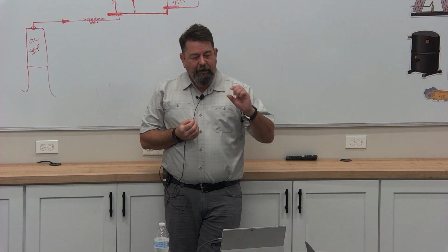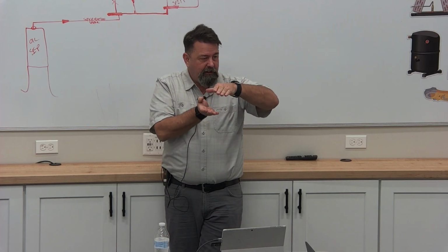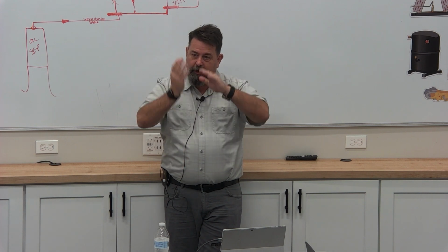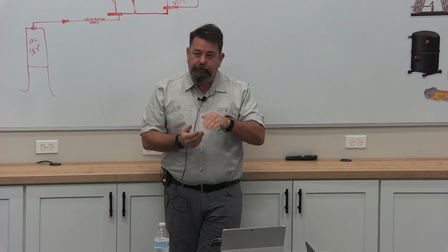Now, the way that pressure is segmented, so it's not all the same pressure, is by the shelves. So this drawing is showing the air coming down. Well, in reality, it's flowing up this back wall, and it's going out of these holes. And when it goes out of the holes, we kind of think of it as shooting straight out. It doesn't. It's coming up at an extreme angle. Comes out of that hole, it's flowing at that kind of an angle.